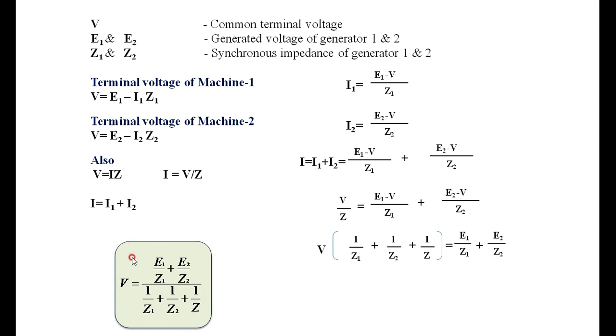Once we know the value of V, and knowing the generated voltages of generators 1 and 2, we can calculate the currents I1 and I2 — the load currents shared by alternator 1 and alternator 2. The apparent power delivered by alternator 1 is V·I1, and by alternator 2 is V·I2. If you want active power, take the real part of the apparent power: P1 equals V·I1·cos(φ1) and P2 equals V·I2·cos(φ2).